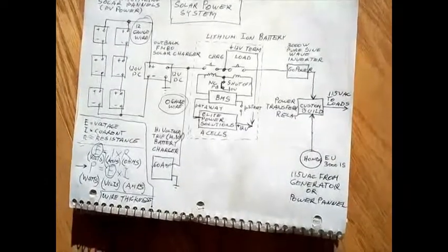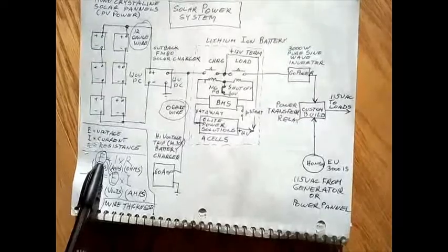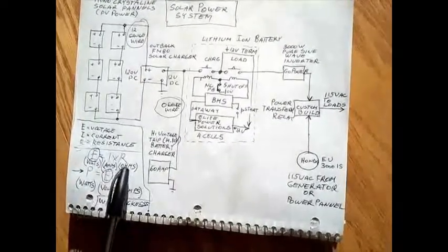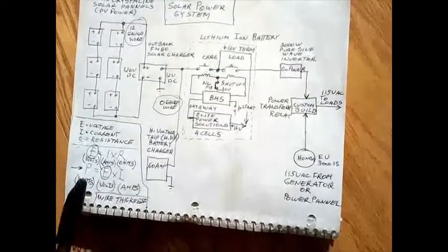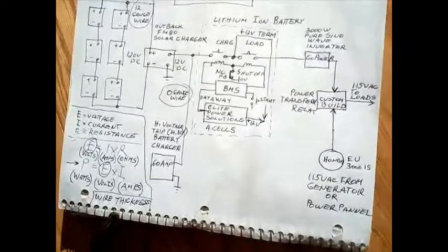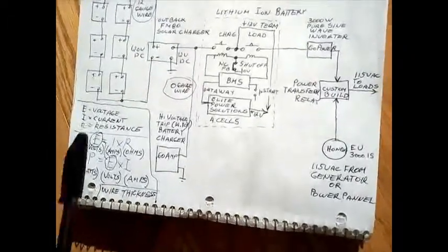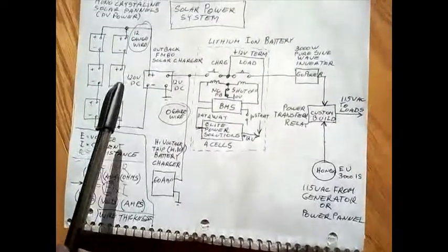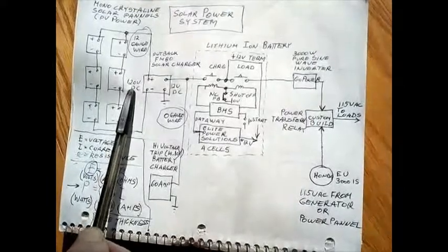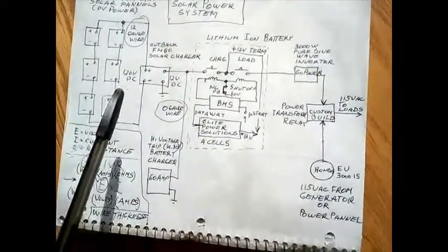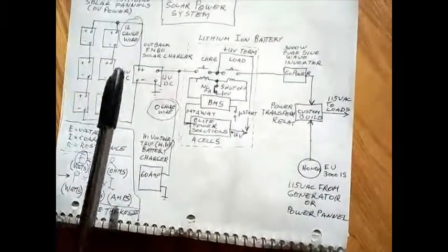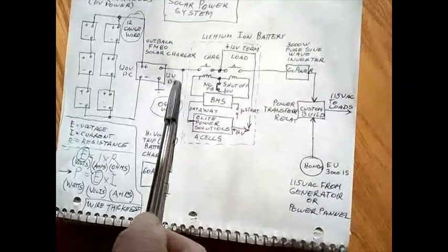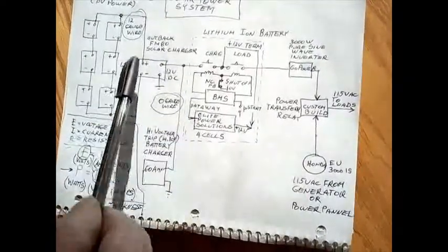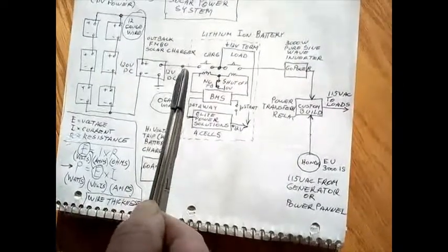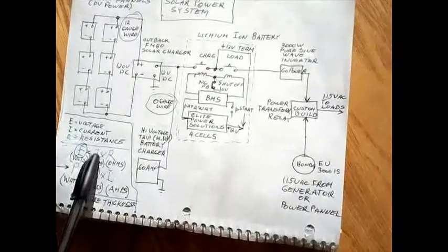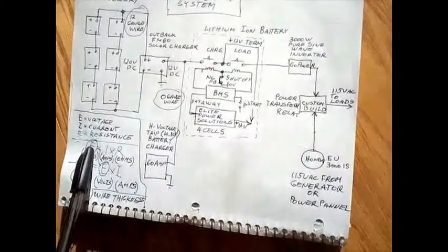The voltage drop across a wire is equal to amps times the resistance. Resistance is opposition to current flow. Now, seeing that power is volts times amps, if you've got a high voltage, 120 volts DC, you're going to have a small current. If you've got a low voltage and the same power, in this case, you're going to have 10 times the amount of current. Because as current increases, the voltage drop across the wire increases.